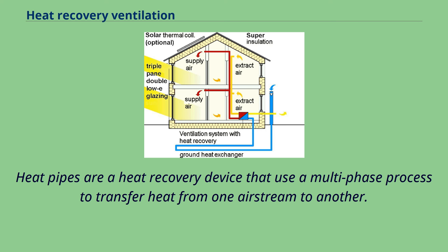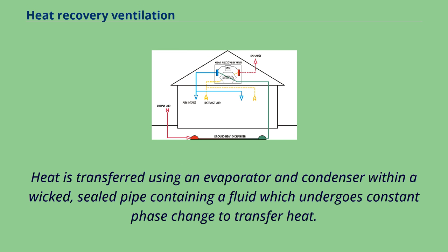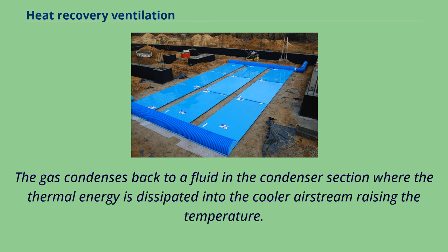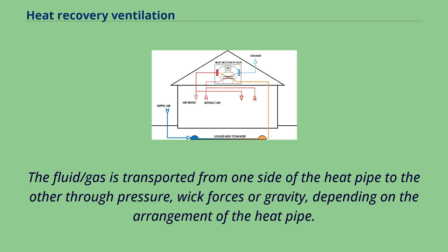Heat pipes are a heat recovery device that use a multi-phase process to transfer heat from one air stream to another. Heat is transferred using an evaporator and condenser within a wicked, sealed pipe containing a fluid which undergoes constant phase change. The fluid changes from liquid to gas in the evaporator section, absorbing thermal energy from the warm air stream. The gas condenses back to liquid in the condenser section, dissipating thermal energy into the cooler air stream and raising its temperature. The fluid/gas is transported from one side of the heat pipe to the other through pressure, wick forces, or gravity, depending on the arrangement.